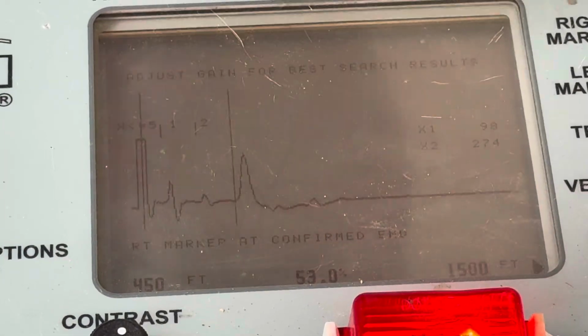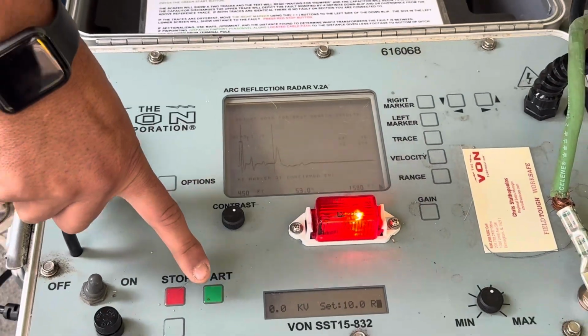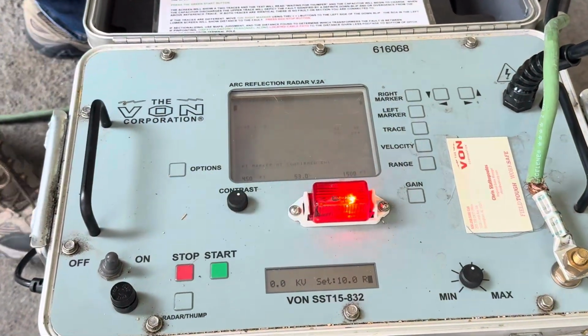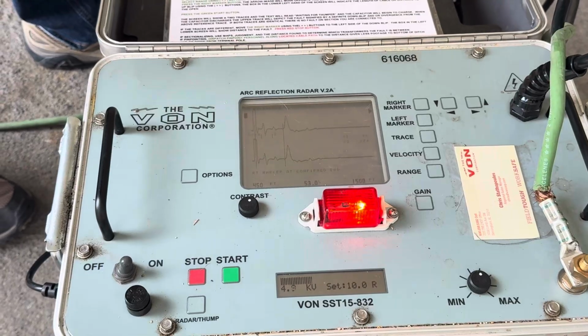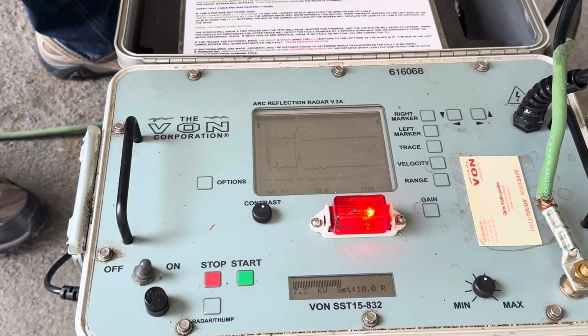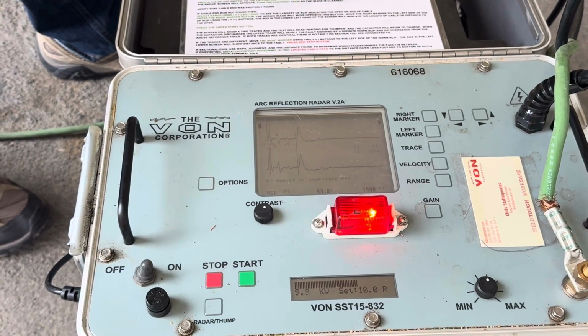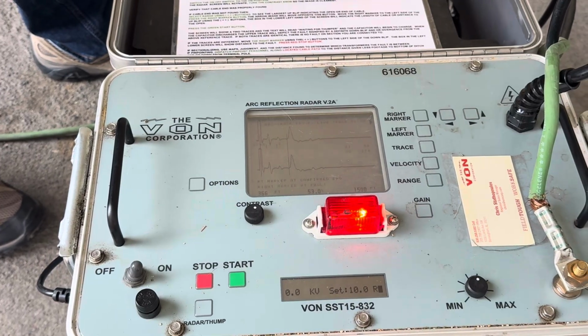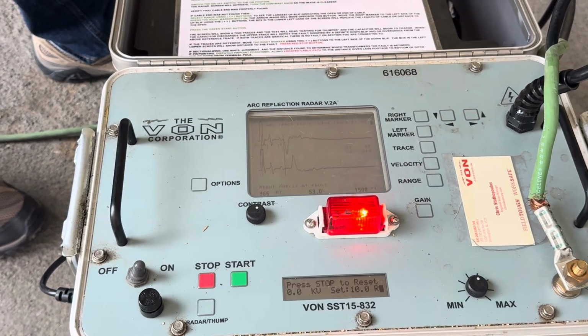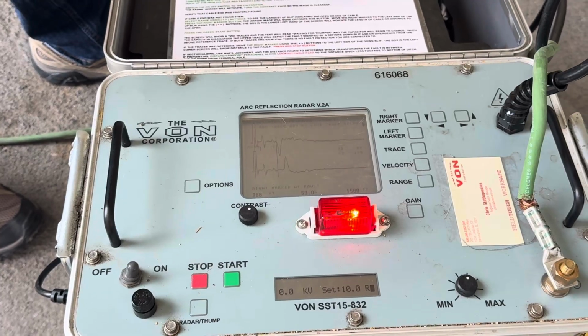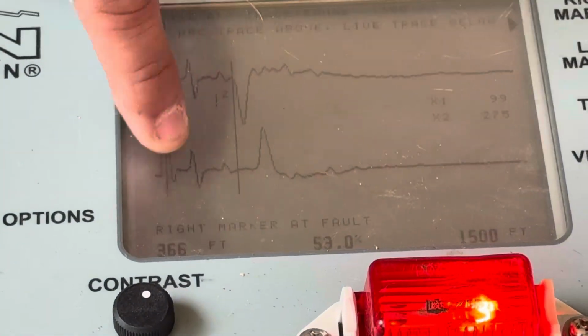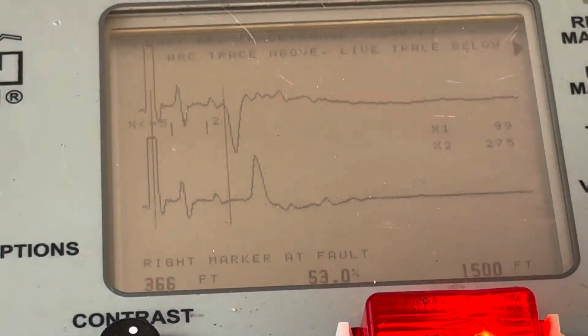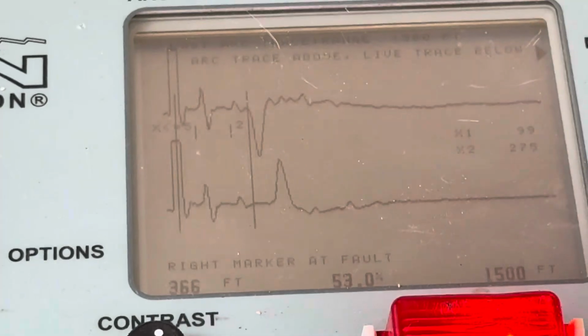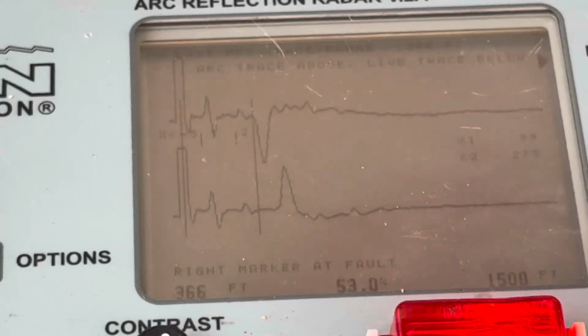Now on this one, I'm going to take my voltage. I don't need to go to 15. We're going to go to about 10. And you notice this has the set point on there, so you always know what voltage you're at. I'm just going to push the start button. We're going to have two transformers on here. Then we have two traces. Right marker at fault, 366 feet away. So it's between your second transformer and the normal open.